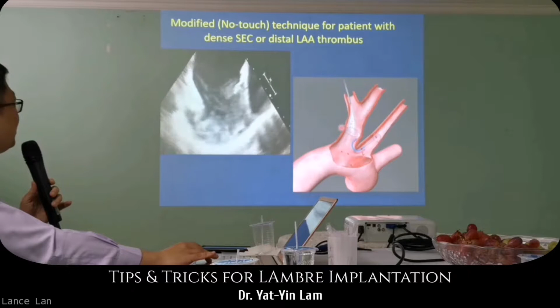So this is the angiogram of measurements. I think for Watchman implant, you only measure this line. Basically, everybody knows how to do. But for LAmbre, because you have additional cover, that's why I also try to measure another one. This is what we call landing zone. This is called ostium. If this tube diameter is more than 10 millimeter, I understood I have to select this special device. Because you know that if it's like 23, you select a 26 device, then the corresponding cover will be 32, because it's 6 millimeter larger. So if you choose a regular device, then it should be okay. But for example, if here is 23, here is 34, you know that if I choose 26, the cover is only 32, so you're not able to cover the ostium nicely.